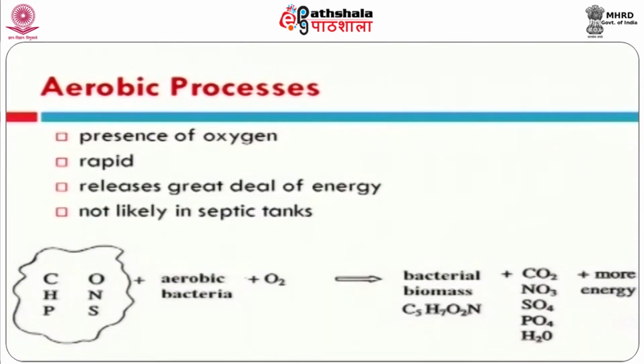In order to maintain aerobic bacteria, the bacteria require dissolved oxygen. In order to maintain aerobic activity in a suspended growth culture, we have to provide a minimum dissolved oxygen content of 2 milligram per liter.